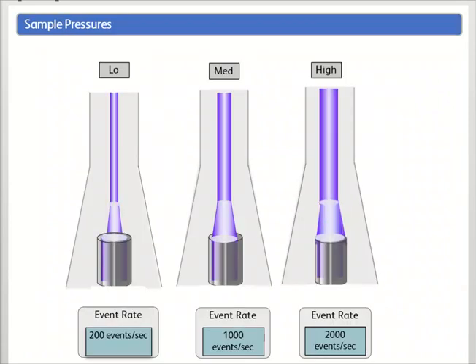The sample pressure settings in BD cytometers are adjustable via controls on the instrument, controls in the software, or both.